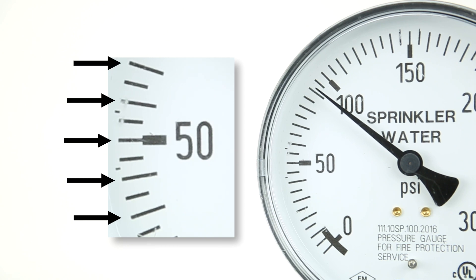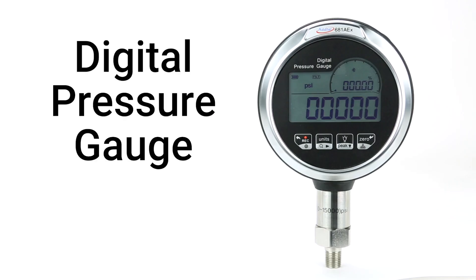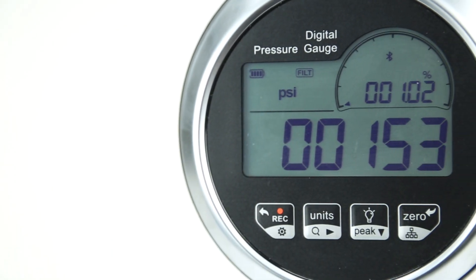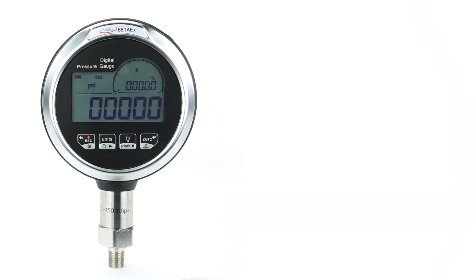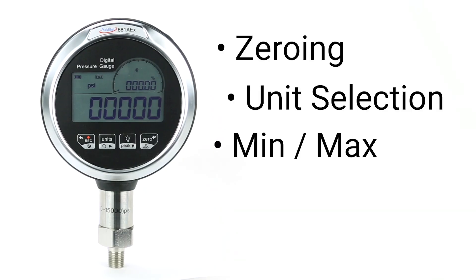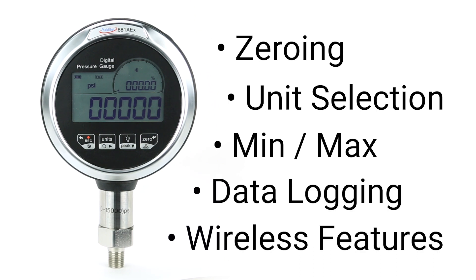Since the accuracy of a dial gauge can only be as high as the number of graduations between the values, a digital pressure gauge is used when more accurate readings are required. Digital gauges function the same as dial gauges, but often have extra functions enabled by their electronics, such as the ability to zero the gauge, change units, find the minimum and maximum pressure values, record pressure over time, and even communicate with other devices.